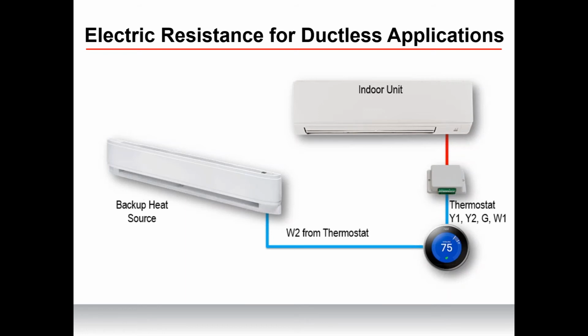Controlling supplemental heat with ducted indoor units is pretty easy. So what about ductless applications? How do we actually control that, other than making someone go down to the floor and manually turn on their electric baseboard when it gets too cold? For electric baseboard, fireplaces, all the different electric options we looked at, it can be as simple as setting the electric heat source thermostat to a lower temperature below the heat pump system set point. Say I set the electric baseboard to 60 or say 65 degrees. I keep my heat pump set at 72. If I drop to 65, then that backup electric baseboard is just going to kick on because you set the temperature to that.